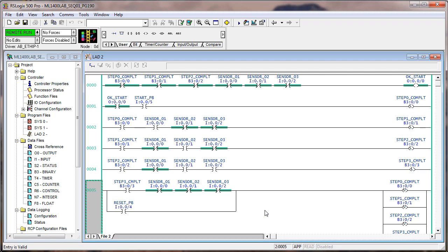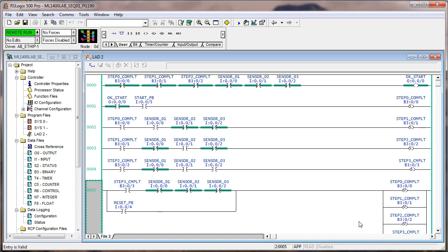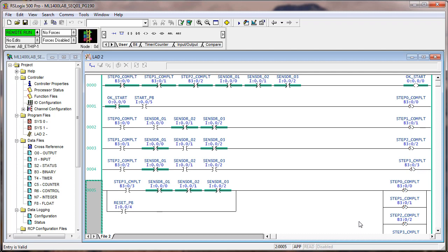So this is really fundamental sequencing logic here. We're using latch and unlatch because that's the simplest to write code for. However, you will find that it is not that popular in the real world because if you latch something, you have to unlatch it. As a matter of fact, we used to have a saying: when you use latches, you have to unlatch the whole world. Now this is not a full process here. Even a simple process is probably going to have 70 or 80 rungs of logic, absolute minimum. And because these are all individual rungs, they're not all going to be in the same spot. So the unlatches aren't going to be right next to the latches. So if you've latched something, you have to remember that you have to unlatch it.